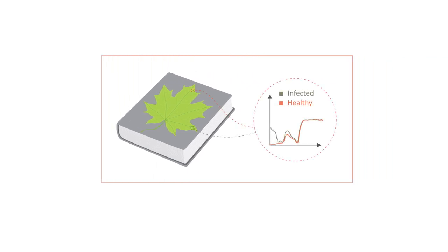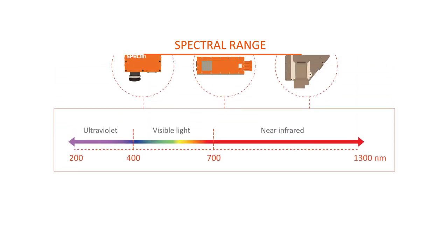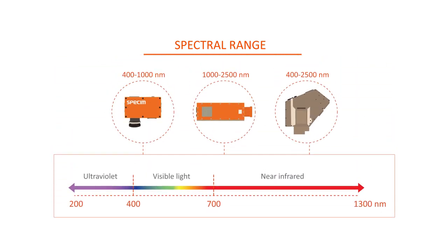We are also able to choose any point of the leaf from the book cover and obtain its full, accurate, and continuous spectrum. This requires that we use all the information of that specific point in every page of the book. We sort of drill a slice of the entire book in order to get the spectral information. So, a hyperspectral camera measures the target in every wavelength that is located in the camera's spectral range, creating a full spectrum for each pixel of the target.